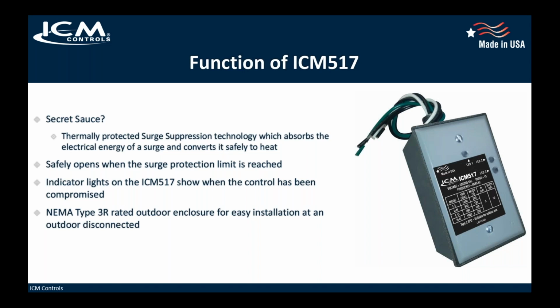This is an expendable item. It is not resettable. Again, it's in parallel with the line, and it's monitoring the line. As soon as something happens within the ratings of the device, it opens up safely, then the control needs to be replaced.